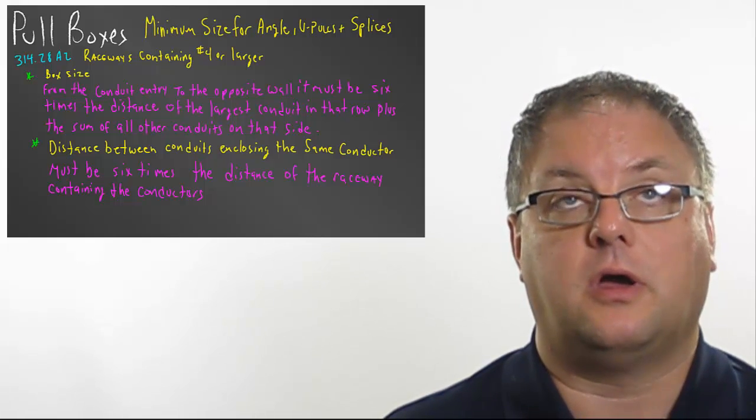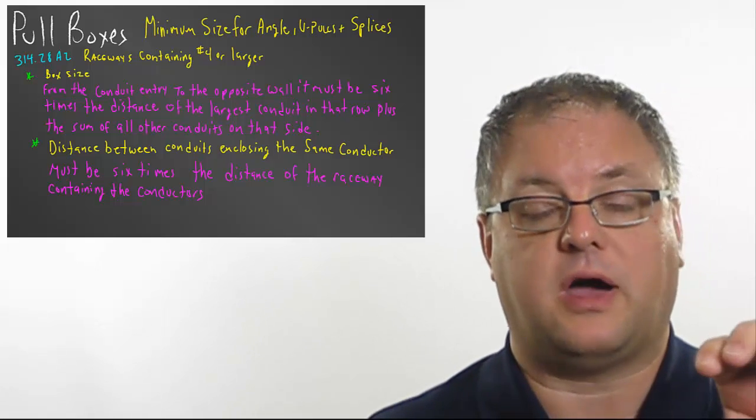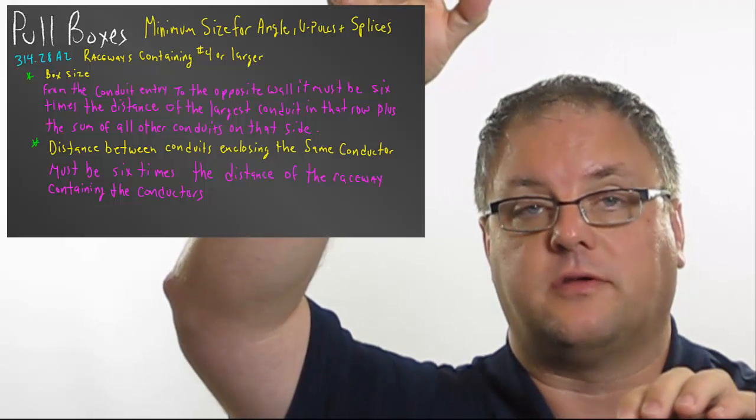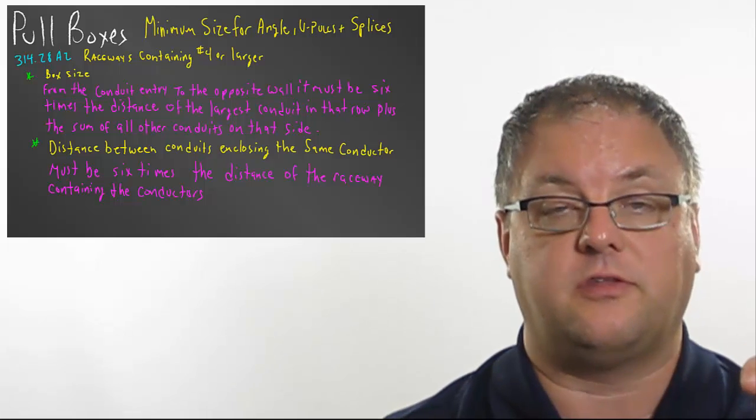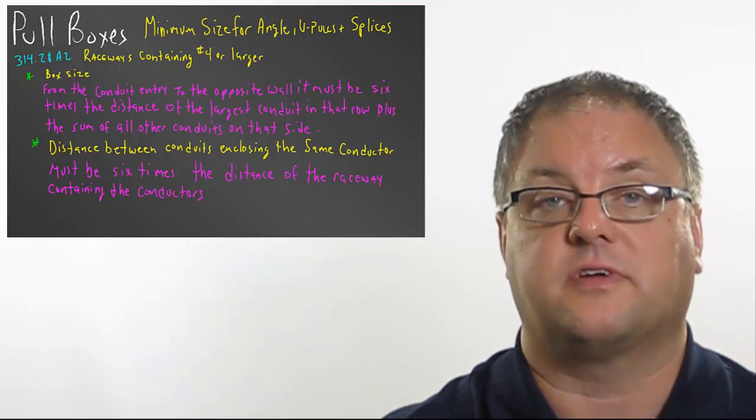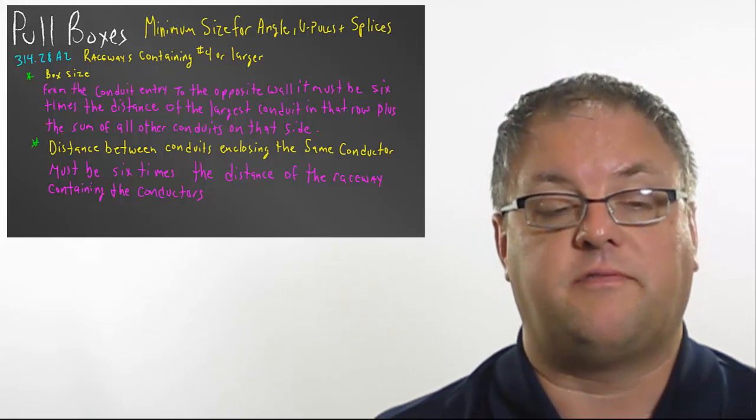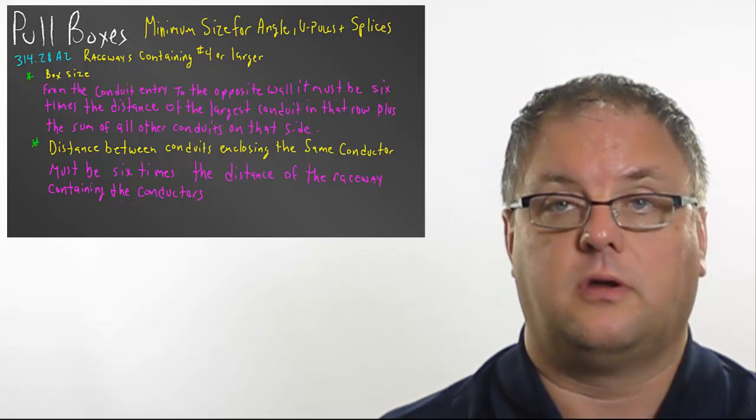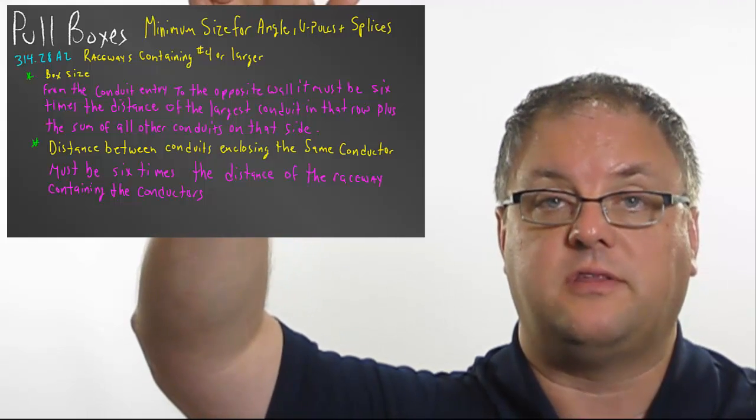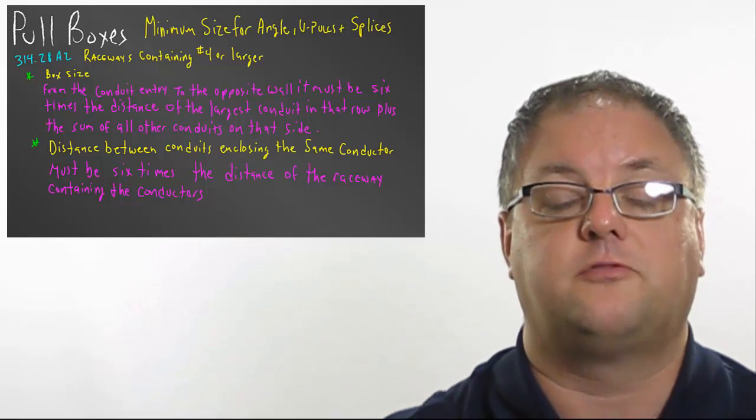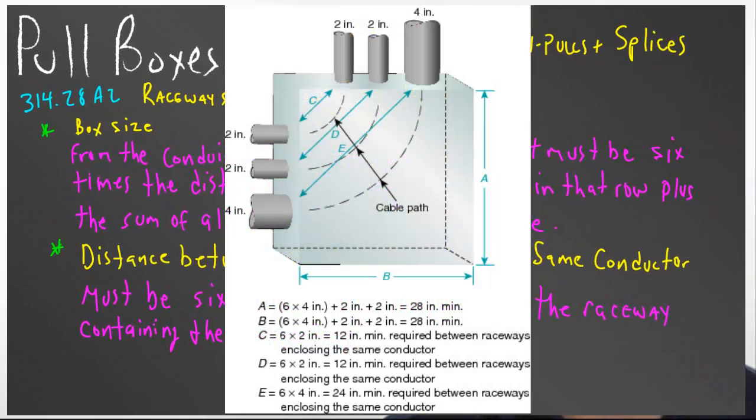Now when you get to another thing that we have to do especially with angle pulls where you come in the box on this side and you come out the box on the other, then we have to maintain a spacing between this conduit and that conduit of six times the size of the conduit that enclosed the same conductor. So if I have a 4-inch conduit coming in here and a 4-inch conduit going out of this box, I then have to maintain a straight line space between those two conduits of 24 inches. In this example you'll see a 4-inch and two 2-inchers in that box and because they come in sides that are 90 degrees to each other that box ends up being square and if you take 6 times 4 plus the two 2-inch conduits now I have to have a 28 by 28 inch box to be able to have an angle pull in there with those conduits involved.